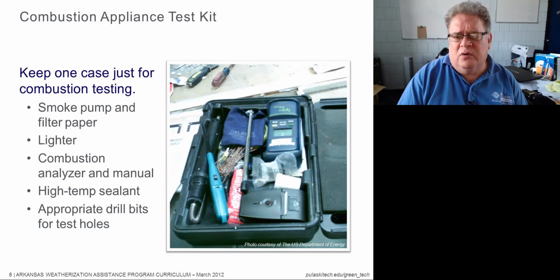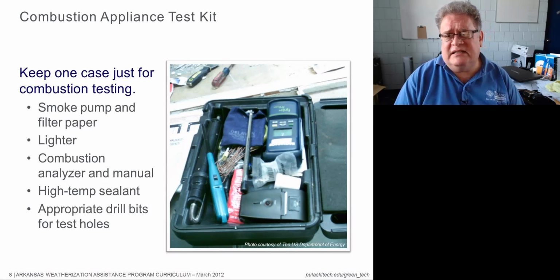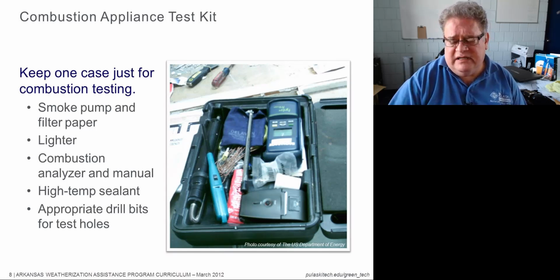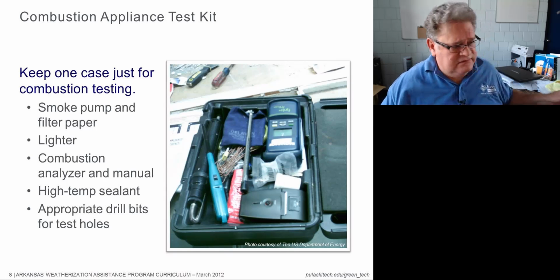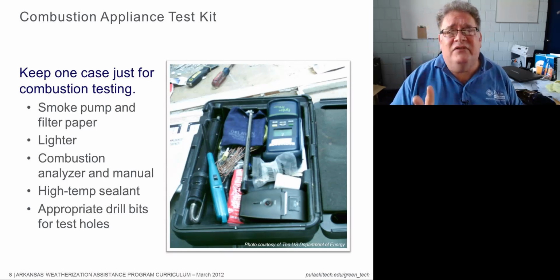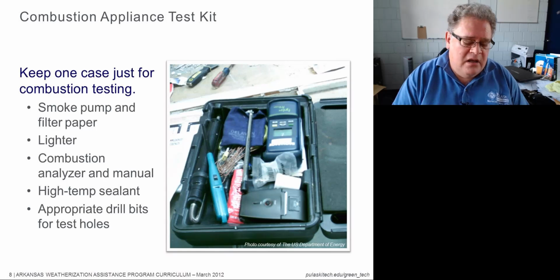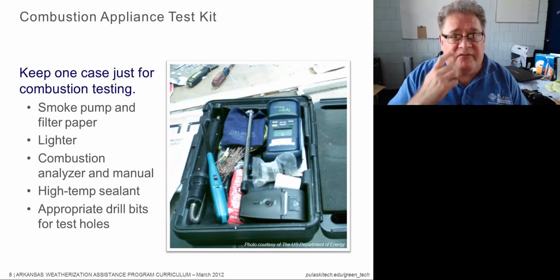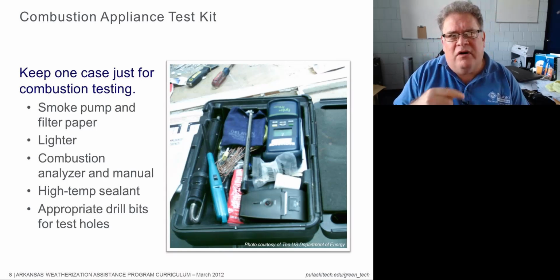If you do fuel oil at all, or solid fuels, well, probably just fuel oil, you're going to have a smoke pump. What this does is allow you to take a sample of the exhaust gas and start to determine whether or not it's safe to put your combustion analyzer in it. Fuel oil can burn with a lot of particles in the exhaust, and those tend to clog or damage your sensor very, very quickly.